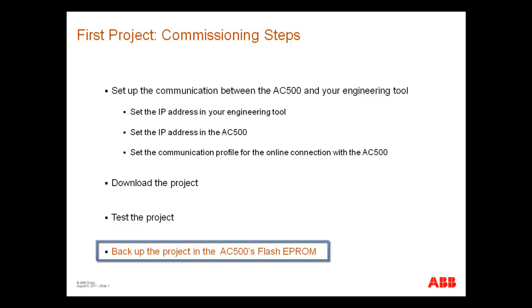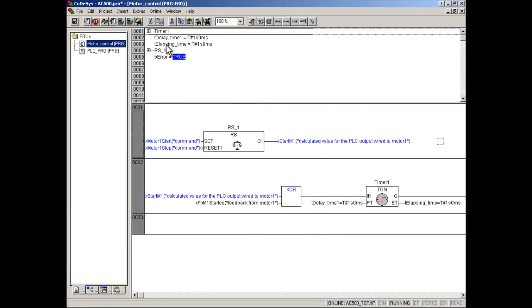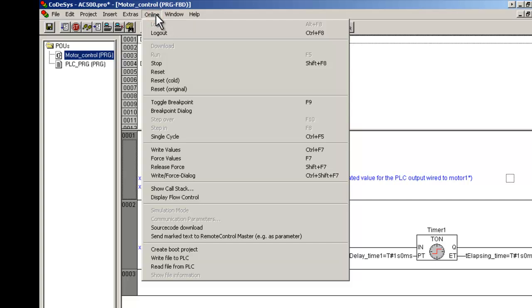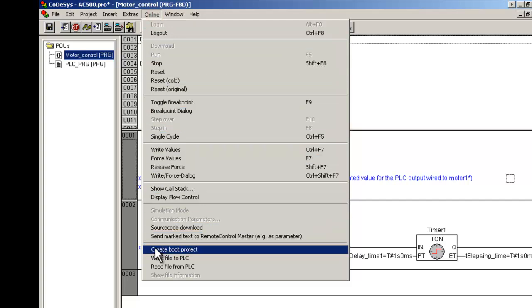Finally, we will backup the project in the AC500's Flash EPROM. The controller can be in Run or Stop mode. Click the menu item Create Boot Project in Menu Online.